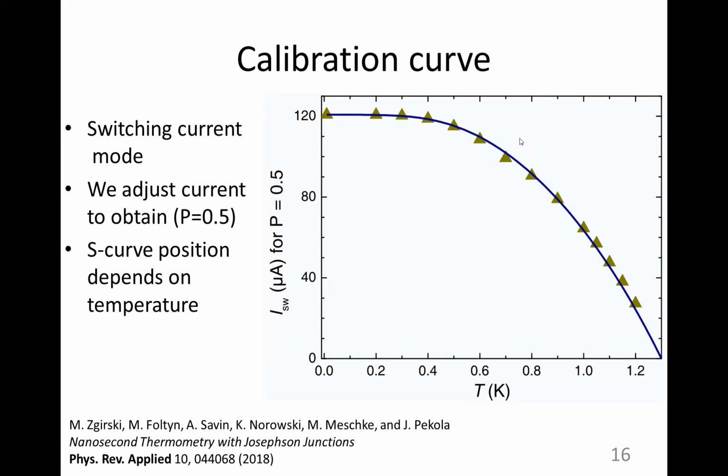So your thermometer is based on quasi-particles, right? Yes. So it means that if you approach absolute zero temperature, you have almost no quasi-particles present, right? Yes. This is the reason why at low temperature there is no sensitivity. So what's the lowest temperature you can measure by this thermometer? Do you see any practical number?